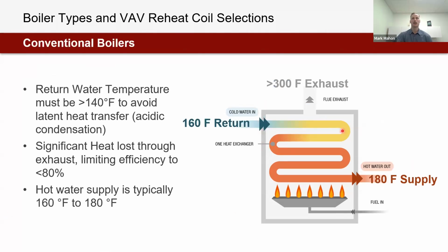Generally speaking, when I look at schedules from across the United States for single duct VAV systems with conventional boilers, we're usually seeing 180-degree supply and 160-degree return.